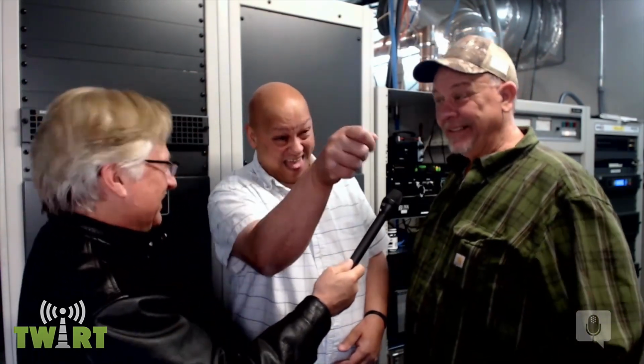All right. What's the procedure when you punch the on button the first time? Are you nervous? Do you need a cigarette? You don't need the broom handle anymore. Because I'm sure a lot of guys remember, especially with some of those old CCAs and McMartins, you used the broom handle so you'd be by the door. With this, it's gradual. You hit the on button, make sure your exciter's on, then you turn your main on, and it just slowly ramps up.